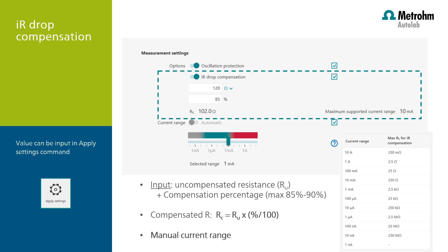The simplest way to use the uncompensated resistance is if you already know the resistance which you would like to compensate for. You can fill the resistance value in the INTELLO software in the Apply Settings command, and specify how much of this value you want to compensate — in this example on this slide it is 85%. Don't go beyond 95% because the potential could run into oscillation, so it is not possible to compensate for 100%. In this case, INTELLO will tell you which resistance — 102 ohm — it will use to compensate.